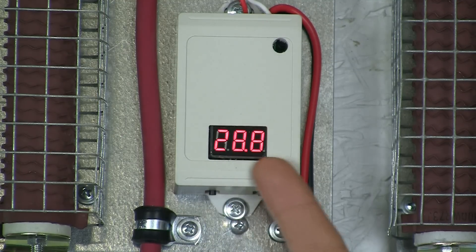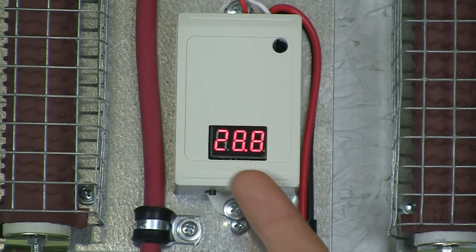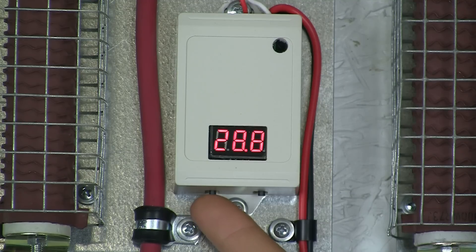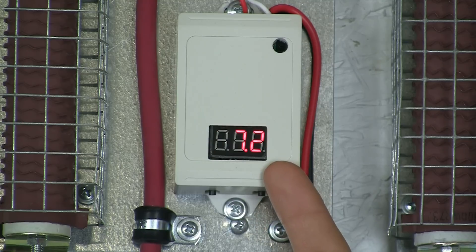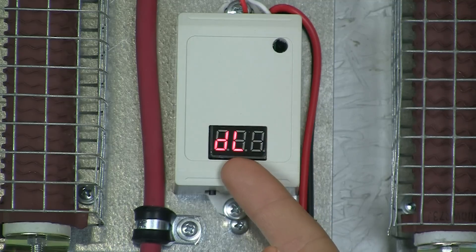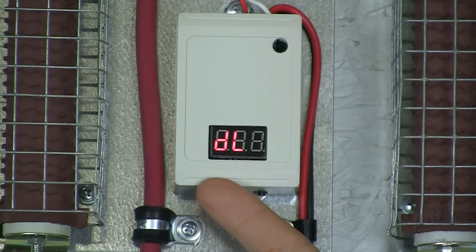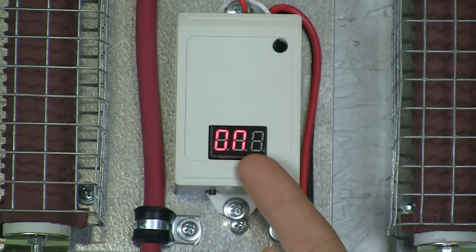Under P3, the first setting is your high voltage disconnect and/or divert point. The second setting is the return-to-charging point. The next screen represents a 0.9-second delay before it diverts. This must be set to ON.